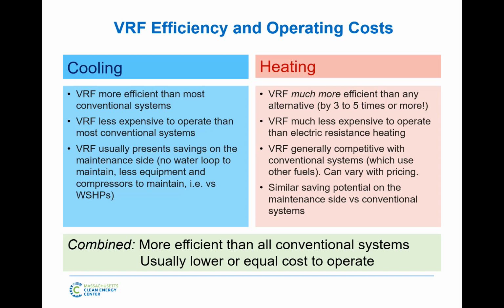Also, there's no water to maintain. Water source heat pump, you have your towers, your boilers, your pumps, heat exchangers to maintain, chemical treatment on the water. With VRF, there's no water. You don't maintain the refrigerant. We don't even have filter dryers in the pipe to change out. We don't want filter dryers in there. It's all internal to our systems. So there's a big maintenance discussion there.